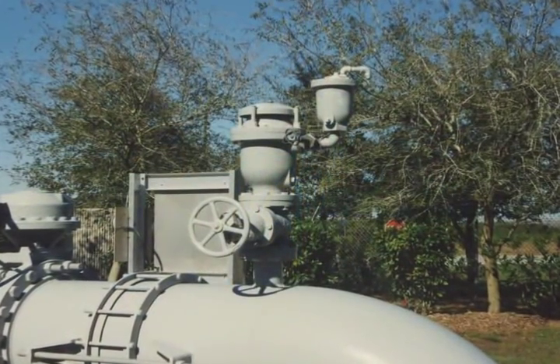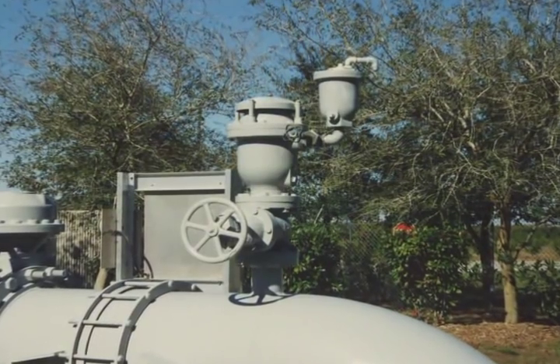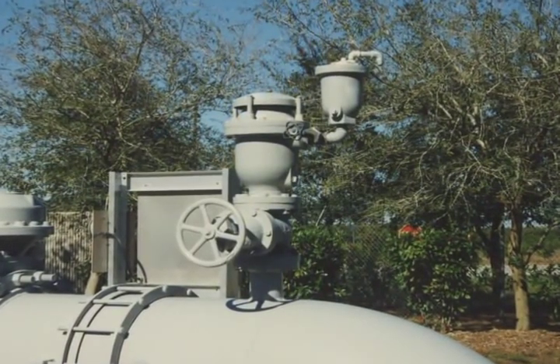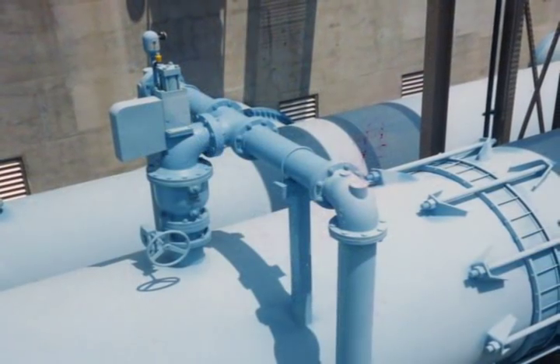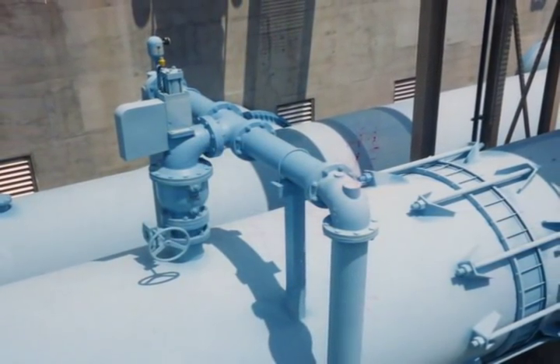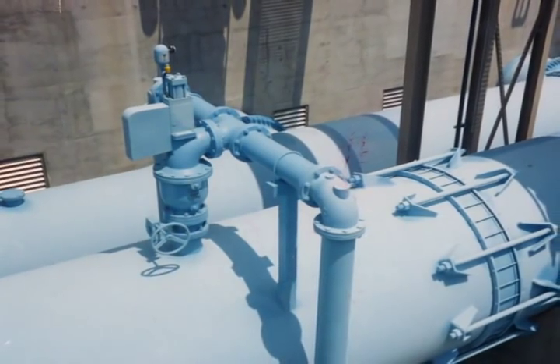Operational problems, especially those apparent at startup, including broken pumps, valves and pipe, as well as faulty instrumentation readings, are often blamed on inadequate thrust blocking, improper pipeline bedding, or other similar circumstances.